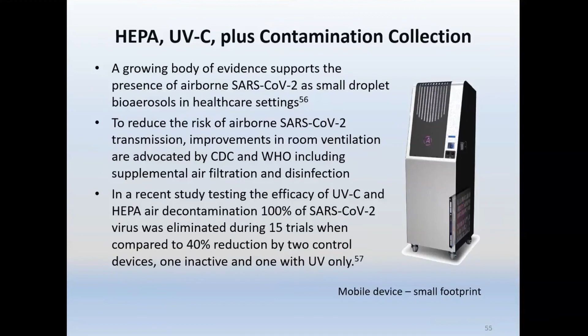They found 100% decontamination of airborne SARS-CoV-2 virus, eliminated during 15 trials, compared to only a 40% reduction by two control devices—one inactive and one UV only. So the addition of HEPA filtration with UV has a wonderful effect on eliminating not only bacteria in the operating room, but viruses like SARS-CoV-2.